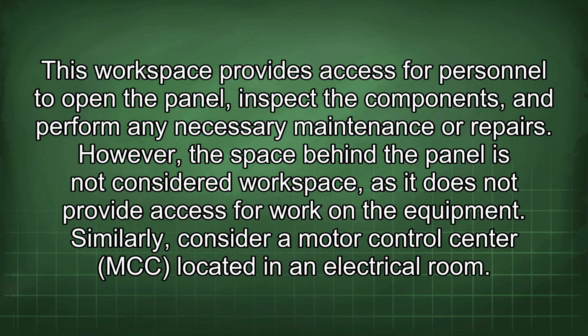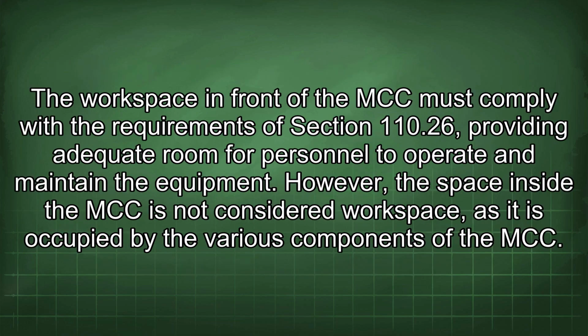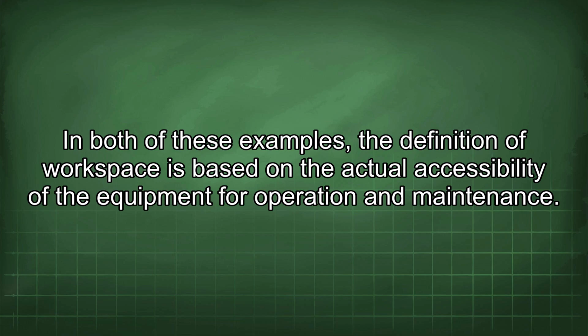Similarly, consider a motor control center (MCC) located in an electrical room. The workspace in front of the MCC must comply with the requirements of Section 110.26, providing adequate room for personnel to operate and maintain the equipment. However, the space inside the MCC is not considered workspace, as it is occupied by the various components of the MCC.